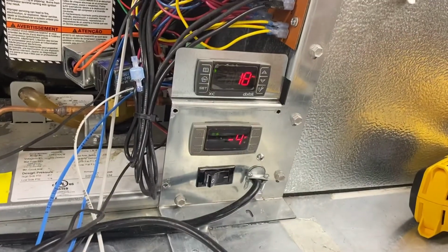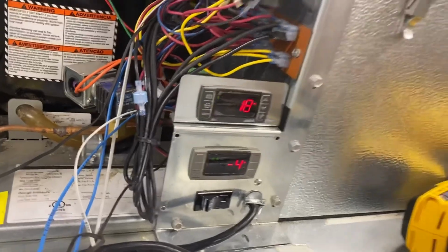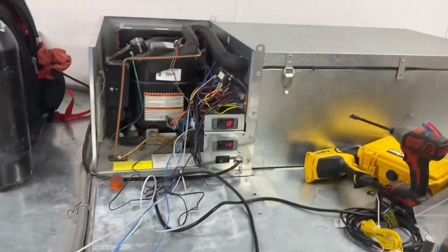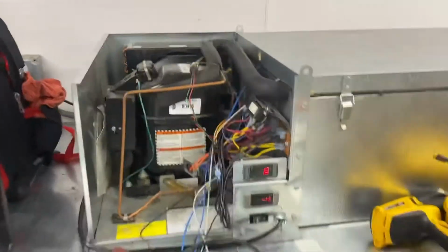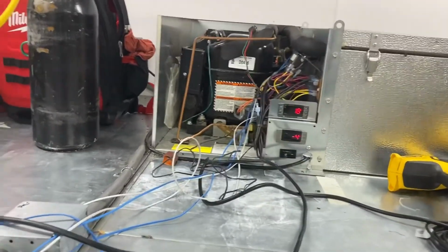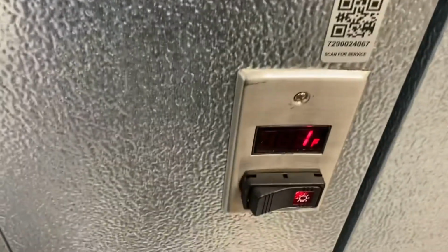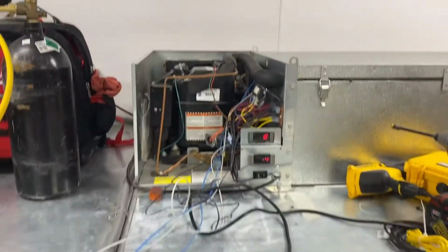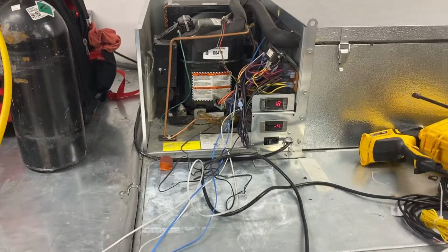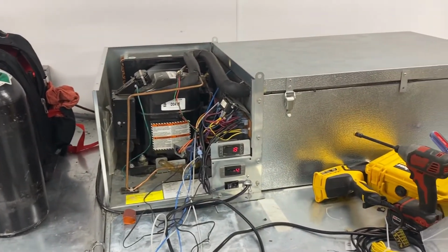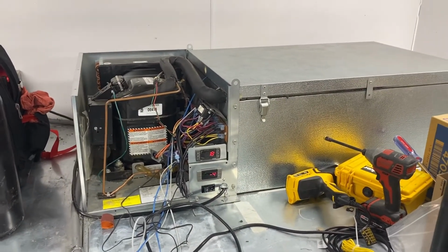So I changed out that thermistor, and it looks like we're getting exactly what we're supposed to be getting. If you take a look here, we're getting -4 now registering in the box, with 18 PSI on the suction line. With -4 in the box, we're registering 1 inside the unit itself. So we're getting exactly the temperature measure that we're supposed to get. That's going to work just fine.